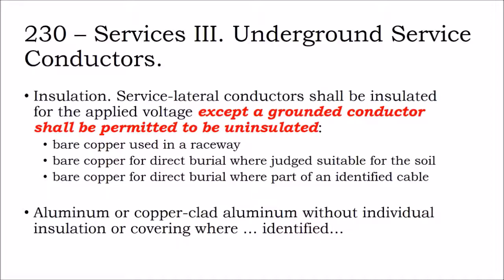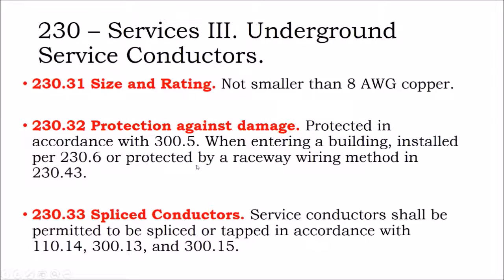Insulation. So service lateral conductors shall be insulated, except a grounded conductor shall be permitted to be uninsulated if it's bare copper in a raceway, or bare copper for direct burial, or bare copper where part of an identified cable. So without getting into that, sometimes you'll be using bare copper on a job site, but otherwise your neutral wire needs to be insulated. That would be a grounded conductor that has insulation on it. We have services, a call out being not smaller than number 8. Then we get a protection from damage where entering a building, they need to be protected in a raceway. Spliced conductors.